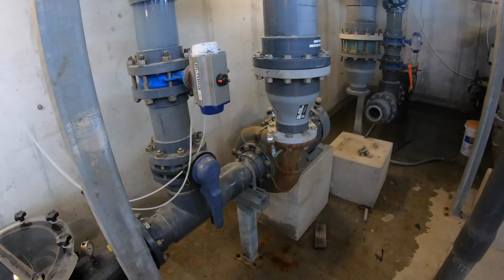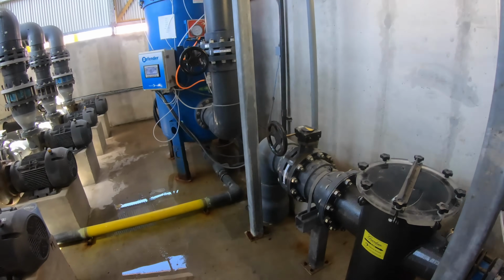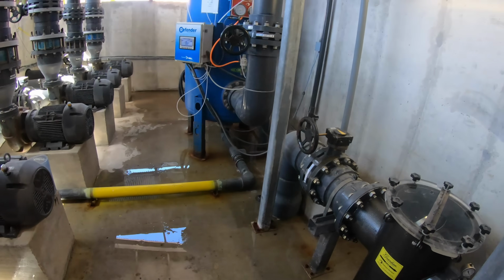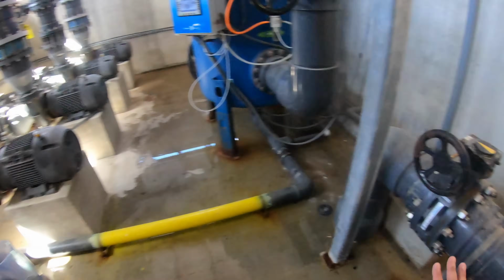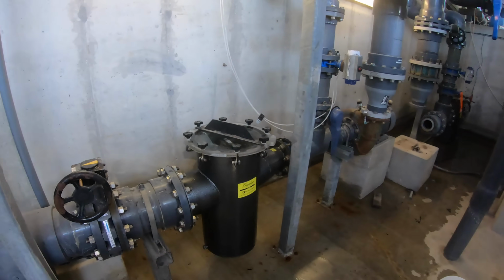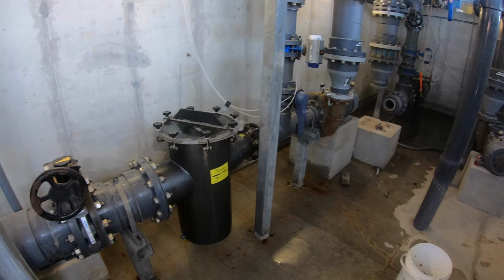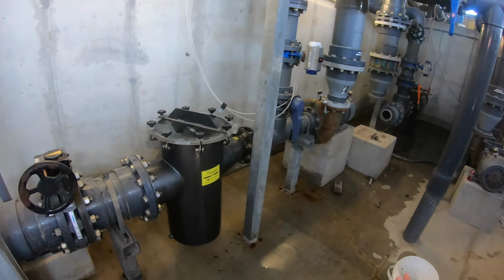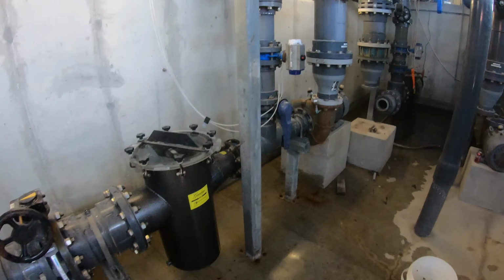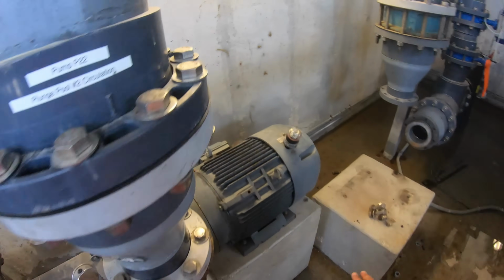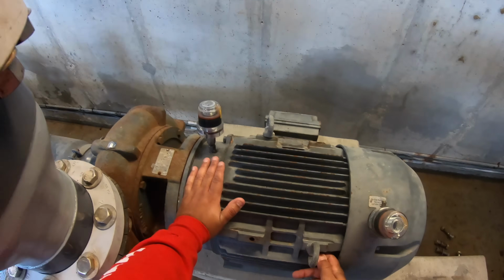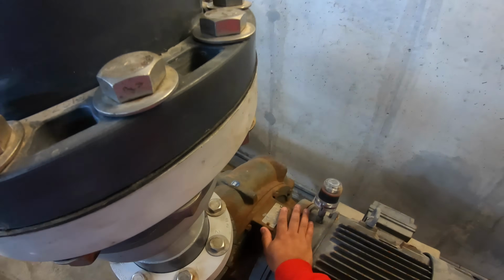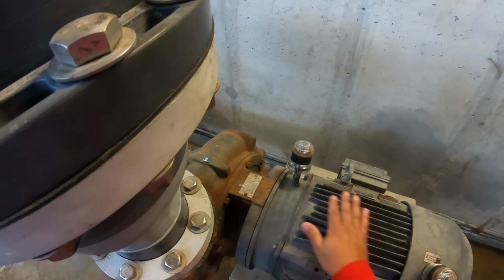Now I'm looking for when we're working through our pre-coat and our filter change and all that. In some of the videos you'll see I put my hand on the motor. All I want to do when I'm checking is to make sure that the motor's not excessively hot. And I'm checking on both sides, both bearings if you will. So there's a bearing here and there's a bearing here. So I just want to feel to make sure that it's not overly hot, okay? And this one feels really good, okay?